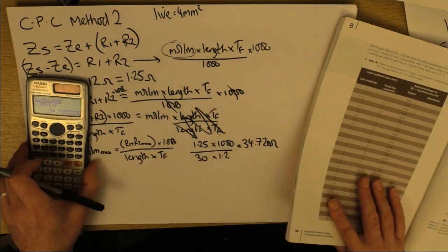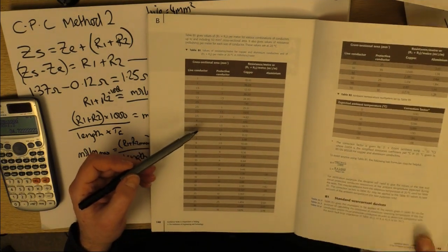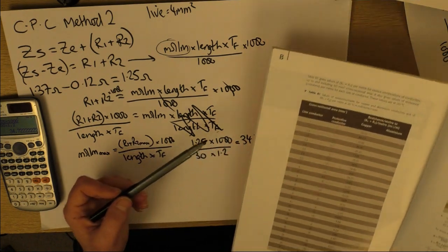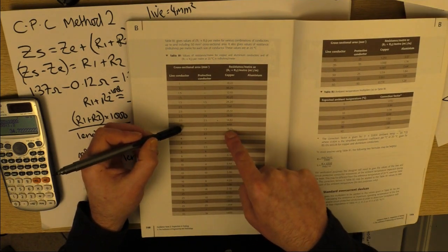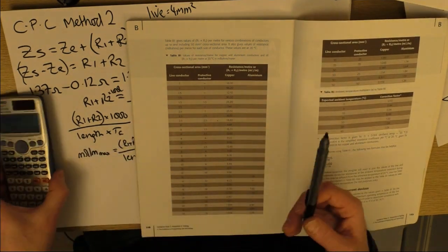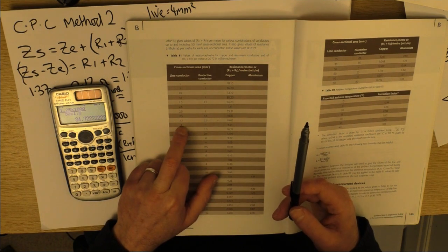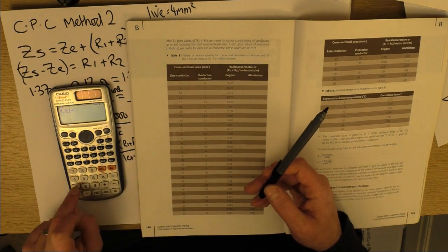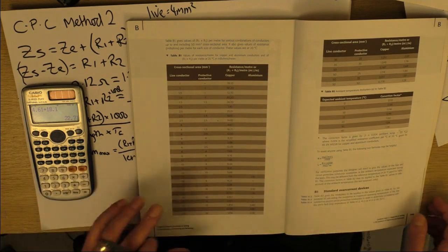milliohms, sorry. Now we've got our live cable already, that was 4 mil. So as long as our milliohm per meter is under this, we're alright. So 4 mil, 1.5, that would work. 4 mil 2.5 would work, 4 mil 4 mil would work, so any of them would work really. We could check the 1 mil, so 4 mil on its own is 4.61, 1 mil on its own is 18.1, and add them together that comes to 22, so that would work as well.